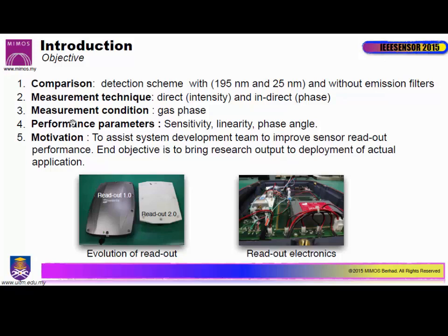One of the problems was they have a very unstable measurement from our sensor. So to compromise, what we did was we performed a test to investigate whether there is a need to use a very narrow emission filter, which indeed in this experiment demonstrated that the system needs to have a good filter in order to get a stable measurement. So my role was to develop the sensor, and at the same time, our system development guys developed the electronics for the measurement of the oxygen sensor.